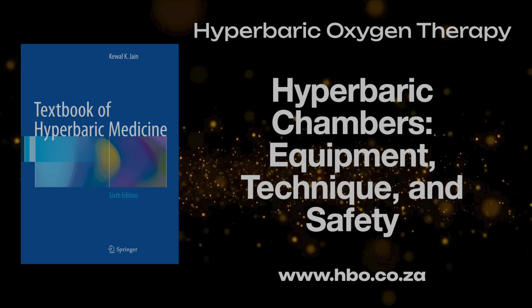Okay. Now, besides the chamber itself, there must be a ton of other specialized gear involved. Oh, absolutely. Ancillary equipment is critical for treatment and safety. Think about oxygen masks and hoods for multiplace chambers. They need a really tight seal, you don't want oxygen leaking into the chamber air, and you need to ensure the patient gets that high concentration. Like pilot masks? Some are similar, yeah, capable of delivering very high O2 levels, usually made of rubber or silicone, easy to clean. Hoods or tents covering the head and neck can be good for treating lesions there.